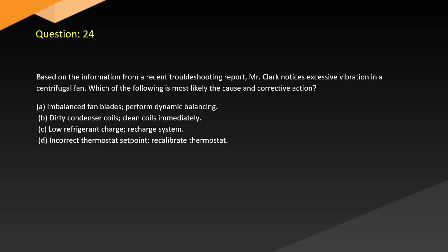Question 24. Based on the information from a recent troubleshooting report, Mr. Clark notices excessive vibration in a centrifugal fan. Which of the following is most likely the cause and corrective action? A. Imbalanced fan blades. Perform dynamic balancing. B. Dirty condenser coils. Clean coils immediately. C. Low refrigerant charge. Recharge system. D. Incorrect thermostat set point. Recalibrate thermostat.